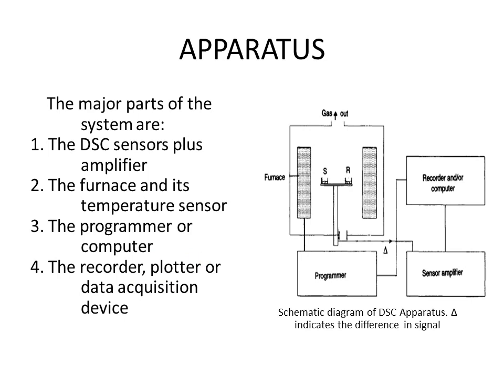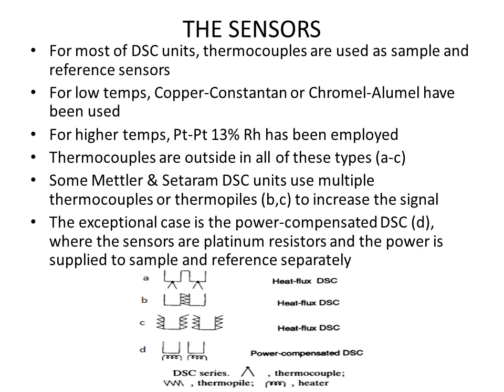For most DSC units, thermocouples are used as sample and reference sensors. For low-temperature work, copper-constantan or chromel-alumel thermocouples can be used. For high-temperature work, the thermocouple may be platinum/platinum-13% rhodium. In the diagram you can see the arrangement of thermocouples in different types of DSC — in all of these types, the thermocouples are positioned outside the pans.